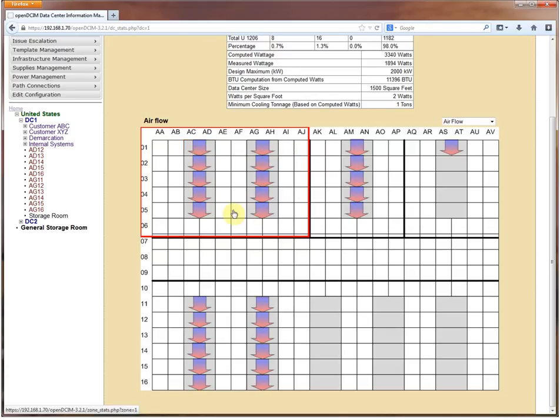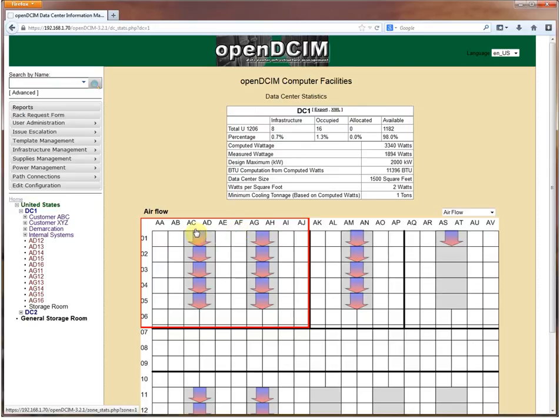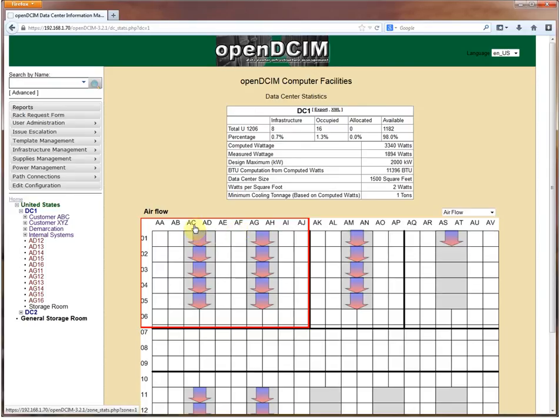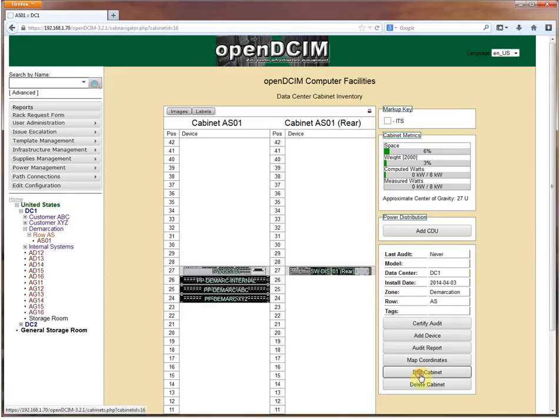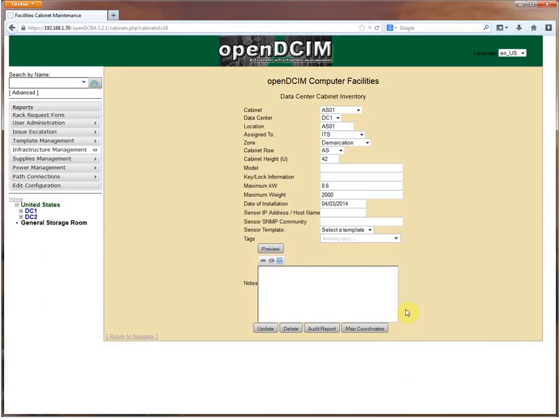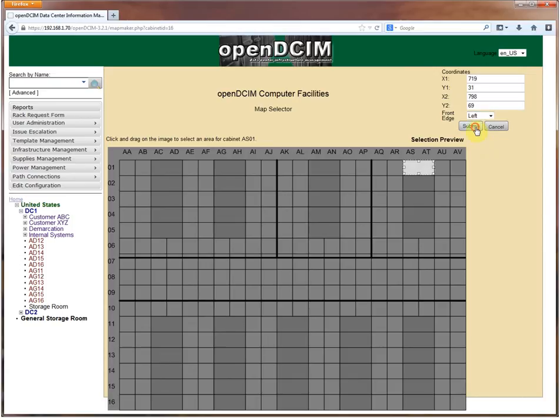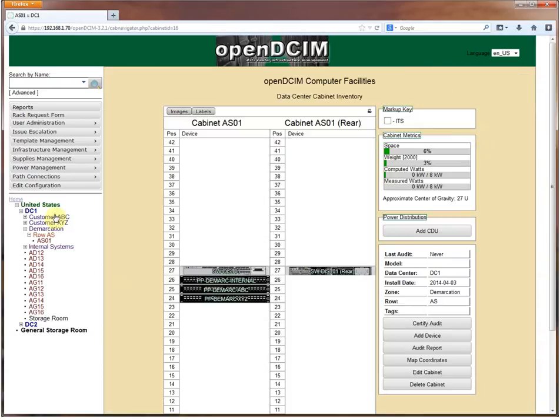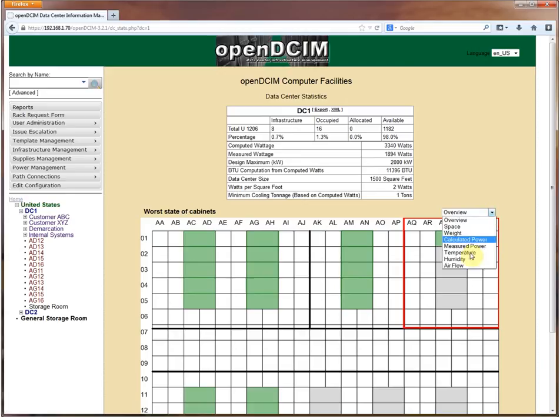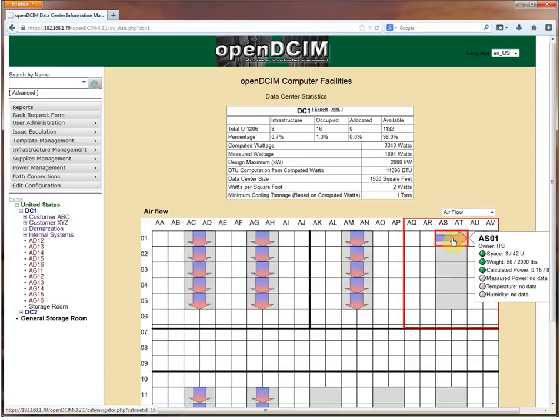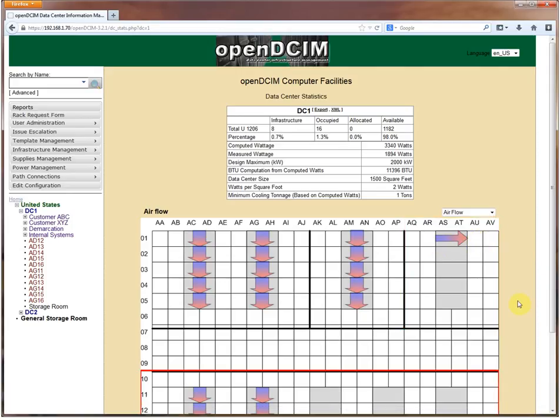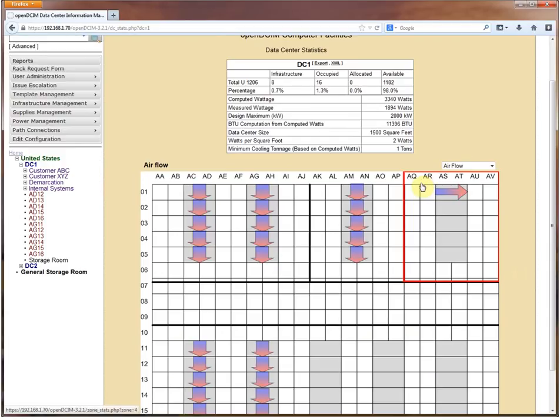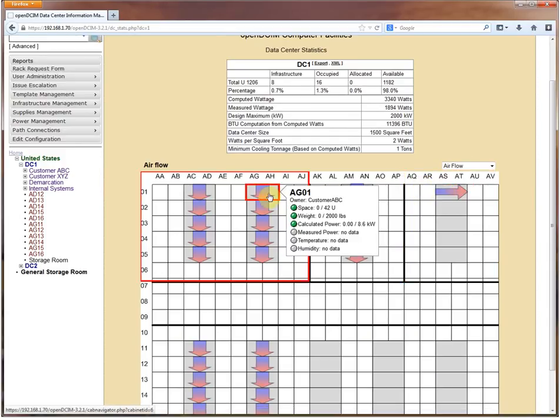Right now everything is still set to the default. The default when you create a new cabinet or when you convert from a previous version of OpenDCIM is the cabinets are the top of the map. There's two different ways to change your airflow. We can go into the map coordinates section and when you map your coordinates you can say that the front edge is the top, right, bottom, or left. If we submit and now we go back over to our data center, you'll see the airflow that we now have a cabinet that flows cold air this side and hot air that side.